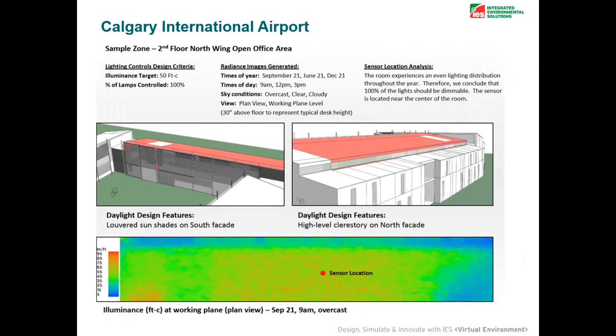With proportional dimming, we see how that changes further, though those systems are much more expensive to add to your lamp fixtures. If you're consulting with a client to sell daylight dimming, you might say we can save 10% with step dimming and 12% with proportional dimming. The question is which one to use, and you weigh them against each other. In an area that's extremely bright all the time, you'd save more with full proportional dimming. It's always about comparing products available on the market and proving how much you can save.